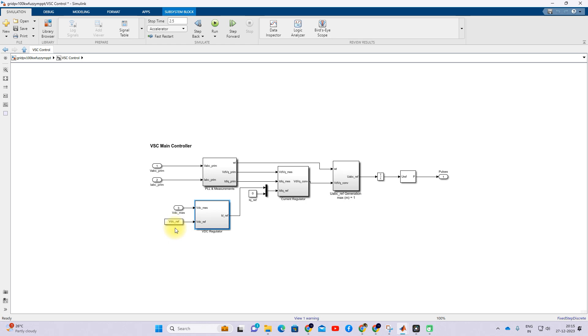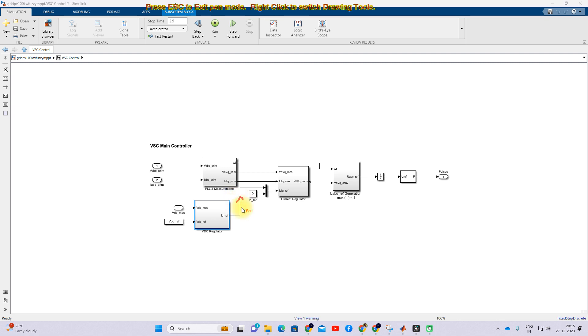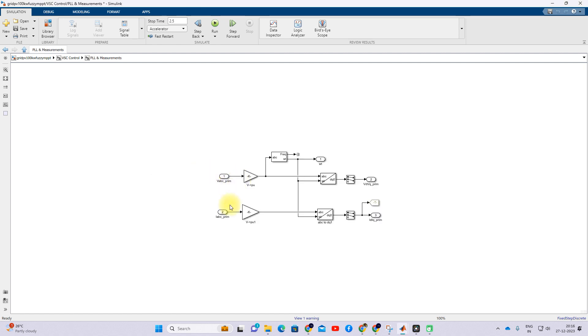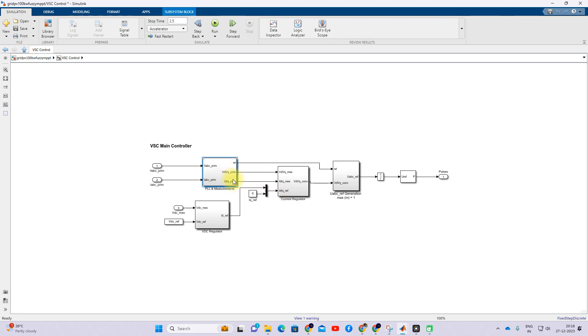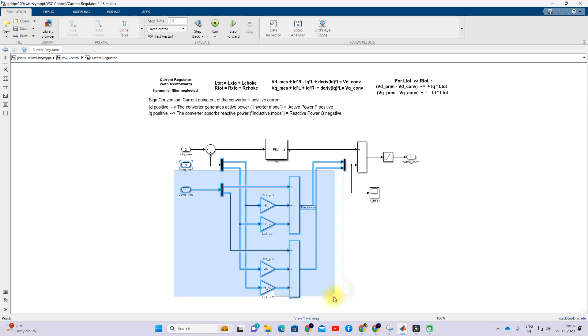We compare the DC link voltage with the reference voltage and process it via a PI controller, which generates the id reference. Since we are only sending real power, we set the iq reference equal to zero. Based on the voltage and current at the secondary of the transformer, we convert from ABC to dq using the Park transformation. After conversion, we have the voltage and current in dq form, then compare id and iq reference with the actual id and iq values via a PI controller, and apply the feed-forward decoupling control concept.